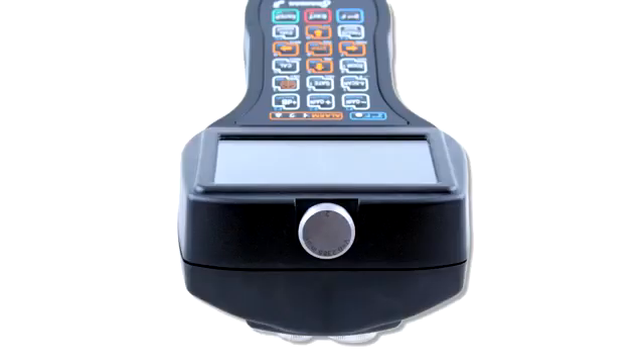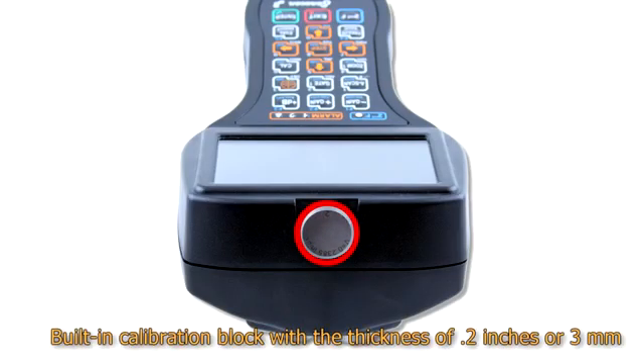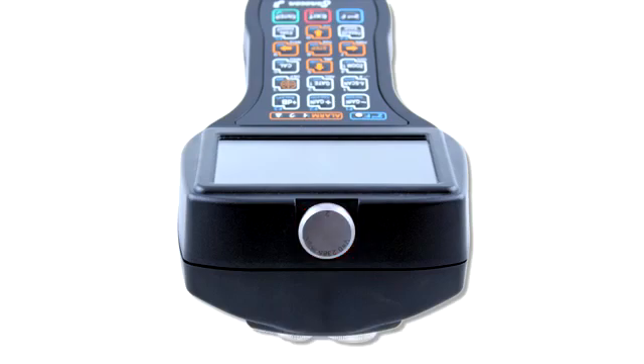On the top panel, a built-in calibration block is placed. Its thickness is 0.2 inches or 3 mm, depending on the regional standards.